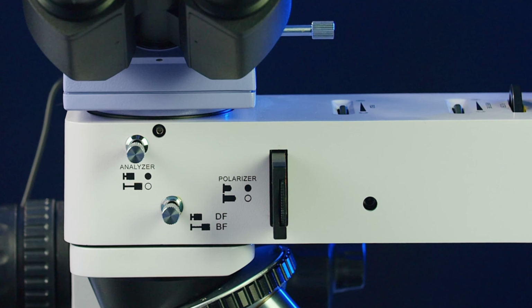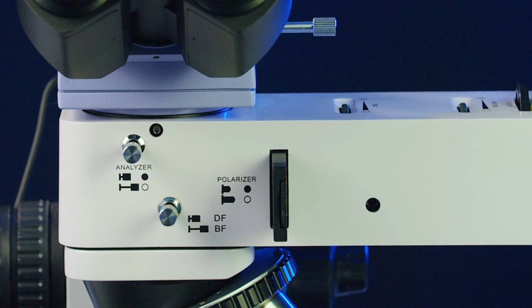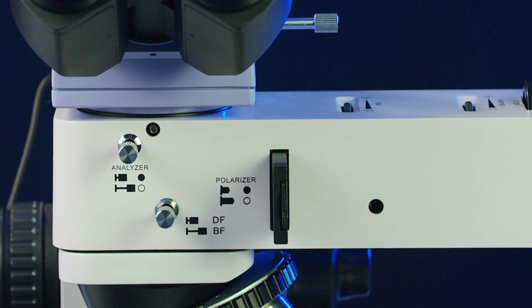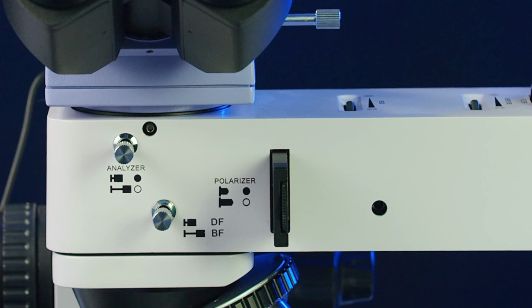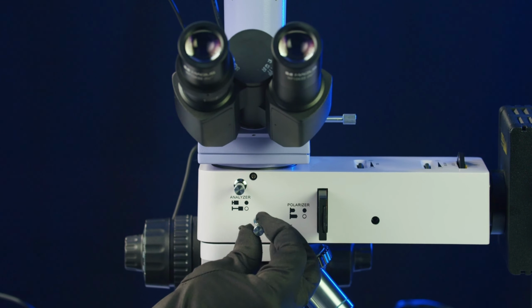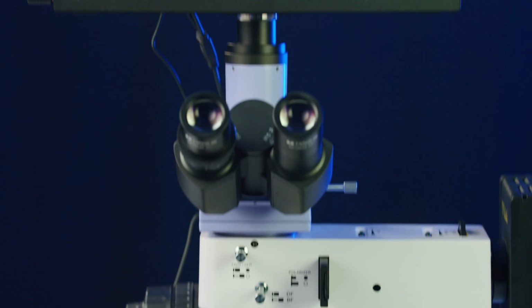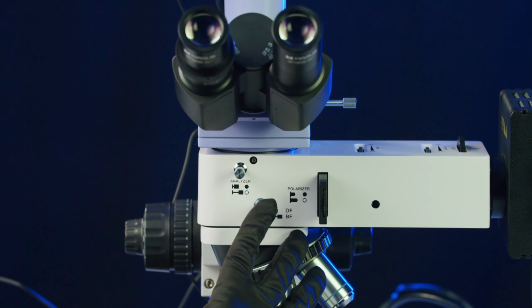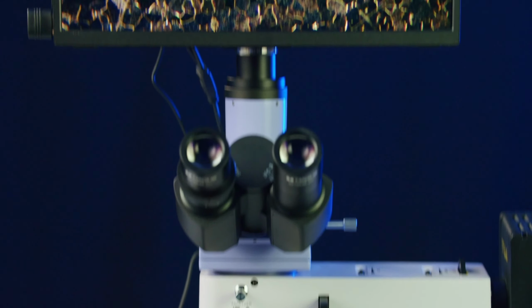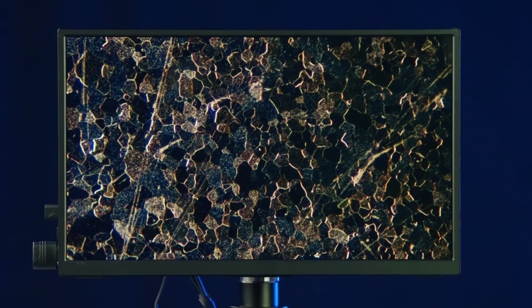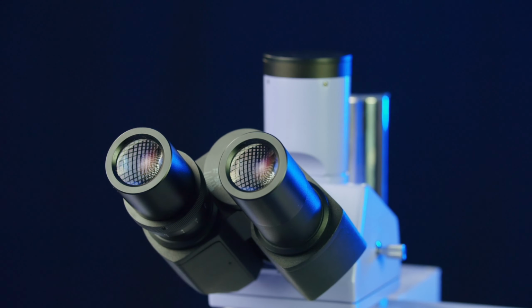The MAGUS Metal 630BD model is equipped with a built-in dark field unit. Switching between bright field and dark field is done using the handle on the illuminator. When the handle is pulled out, the illumination passes through the objective lenses and the microscope operates in bright field mode. When the handle is pushed in, oblique illumination is activated and the microscope operates in dark field mode. Objectives marked with BD support both methods.